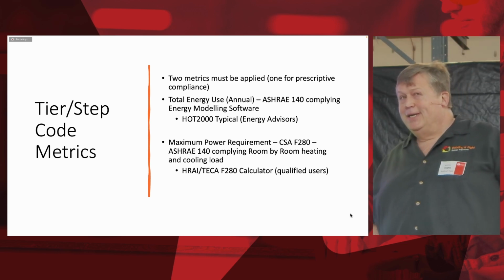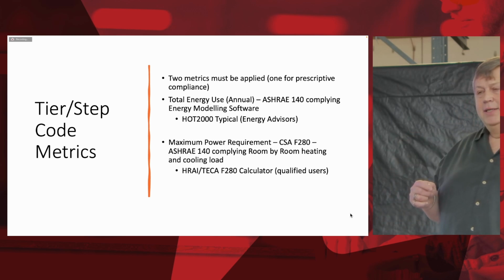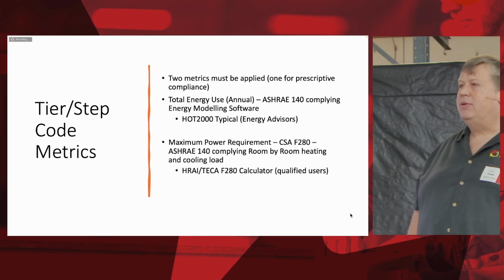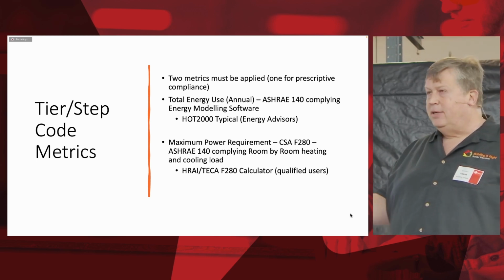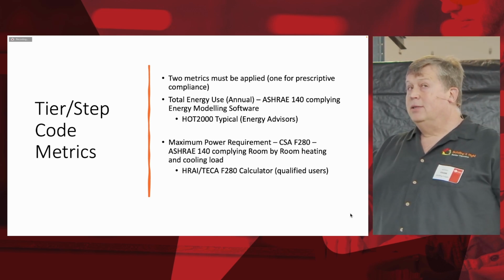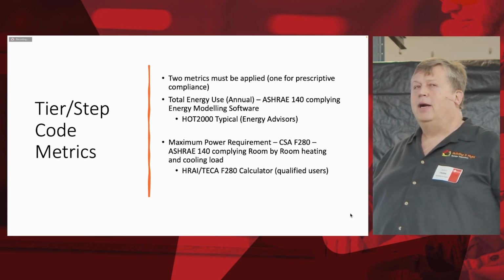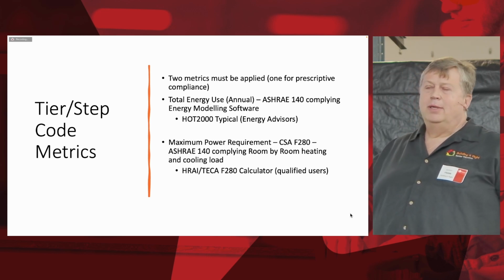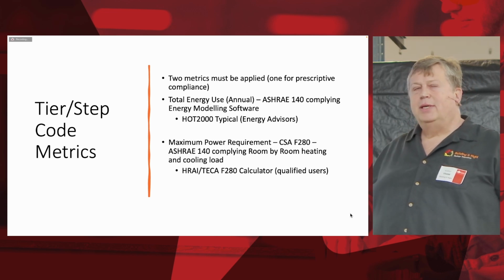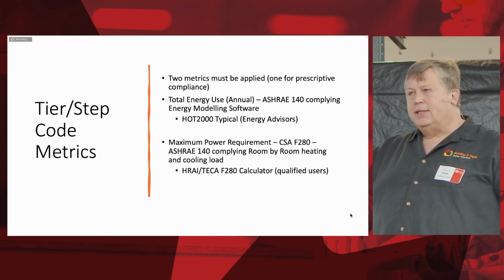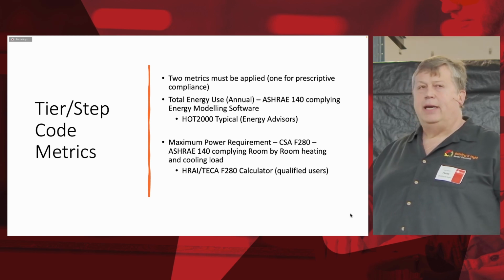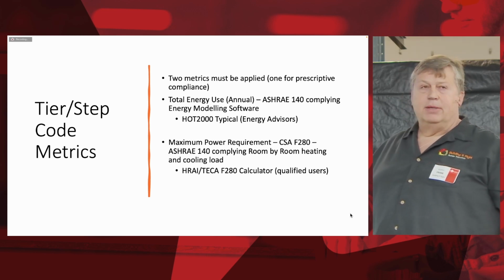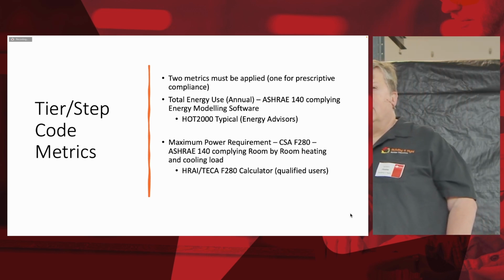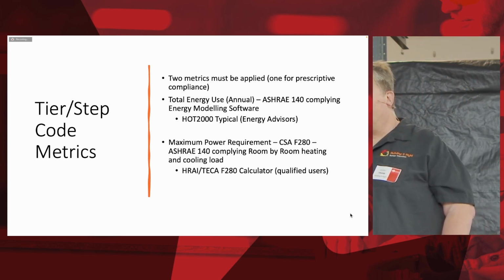So if we do that, what do you know about solar heat gain and solar overheating on a south-facing bedroom when you've completed your design and you put your window spec in there? You know exactly what that room will require on the hottest day to maintain cold, and the impacts of the solar heat gain coefficient. You can change it and rerun that F280, and it'll tell you what impact that has on the ultimate energy or power load that's going to be required to maintain comfort in that house. It'd be pretty handy too if you had to prove it for one room.